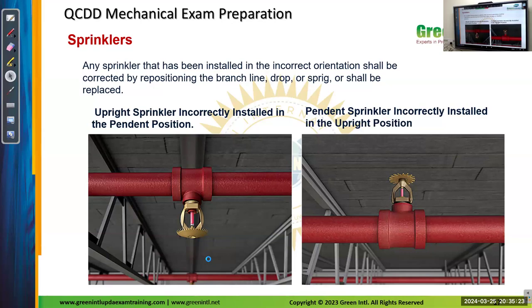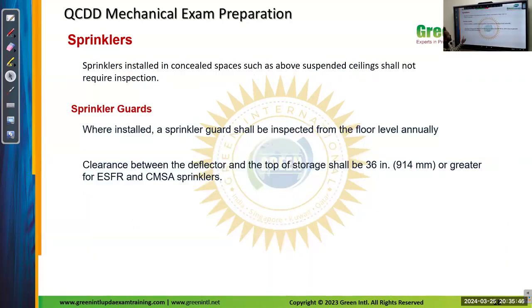So any sprinklers that have been installed in an incorrect orientation shall be corrected by repositioning the branches in the line. It means an upright sprinkler incorrectly installed in the pendant position. This is not a design fault; it is an installation fault. So we have to change the sprinklers. And sprinklers installed in concealed spaces such as above a suspended ceiling shall not require inspection. Sprinkler guards, where installed, shall be inspected from the floor level annually.